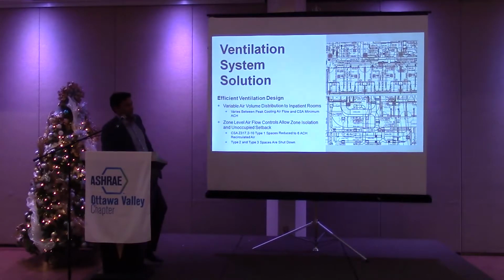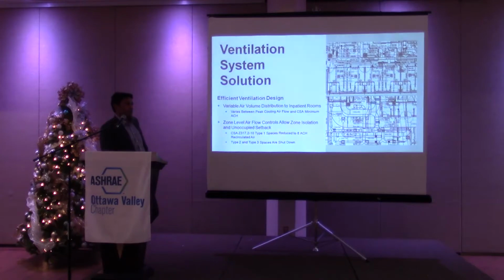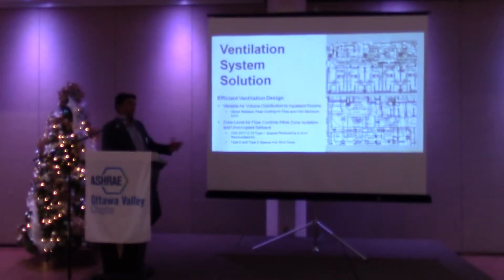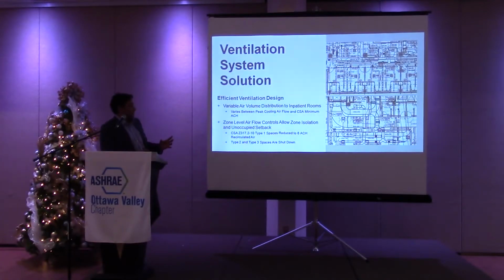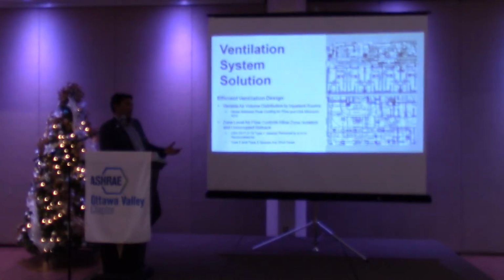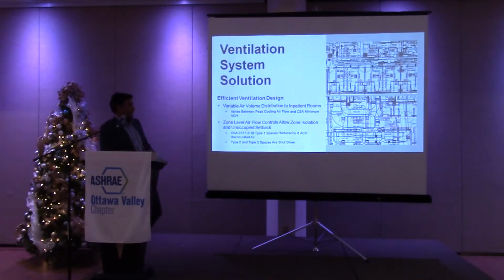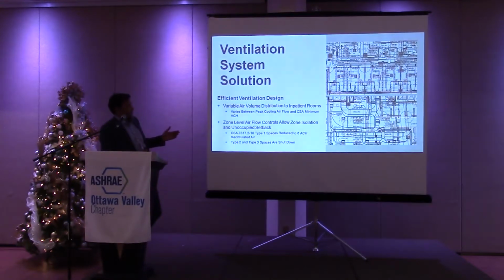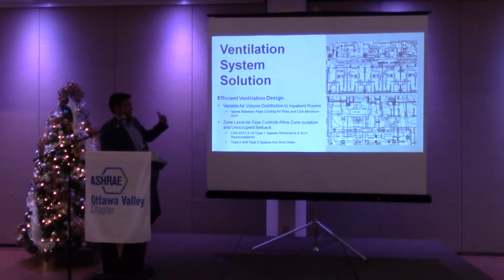One of the other things that we looked at was how to deal with unoccupied times in the hospital. So there's a number of departments and sub-departments that operate different hours. And the CSA standard allows you for certain type spaces to reduce the air changes per hour or actually shut it off altogether. This is a 24/7 facility, so there's a number of spaces that require air flowing through it all the time. Even the ORs. When ORs aren't occupied, you can normally drop down to 6 air changes per hour. Normally you have 20 air changes per hour.